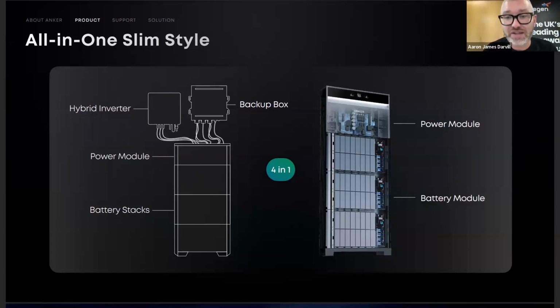To the right-hand side of this picture you'll see the power module, i.e. the inverter. Single phase inverters weigh 19 kg, and 3-phase inverters weigh 30 kg. Then we have the battery modules in that picture, each a 5 kilowatt hour system. So in theory what you see there is a 15 kilowatt hour system with its inverter on top. But as mentioned, you can have up to 6 of these batteries to one inverter, one power module, and then run parallel multiple times.